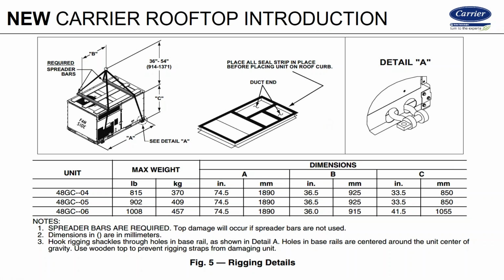So always look ahead of time at what you're dealing with. You may say, hey, I've got a concentric duct setup, or just a nice duct setup, very little static pressure, but I use a curb adapter on it. And so you ordered a low static unit thinking, well, hey, I have no static in my ductwork, or it's concentric, so I'll go with a low static unit. Now you set it on there and it doesn't perform because you really needed a medium static unit to overcome that adapter curb.